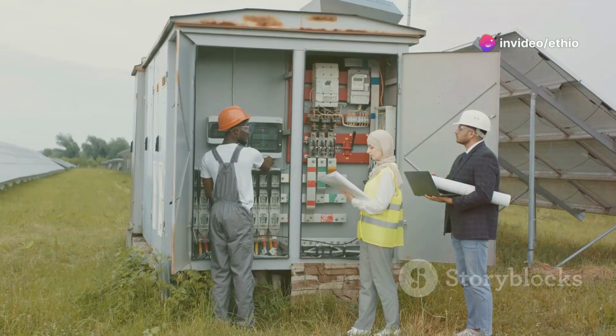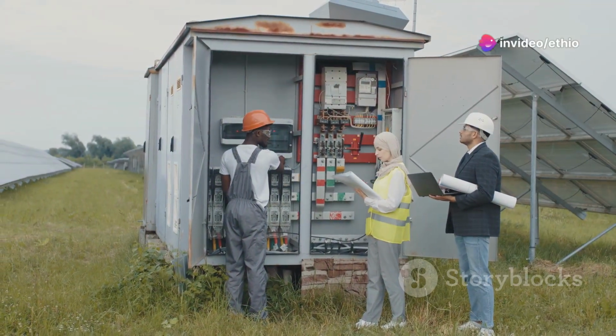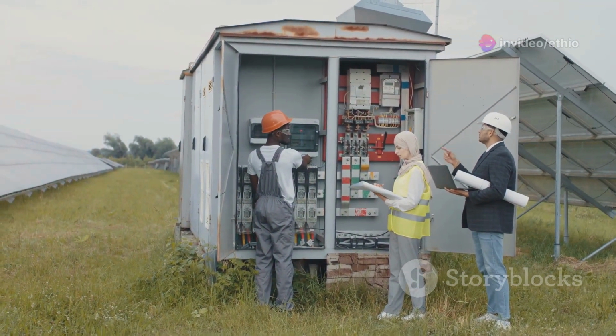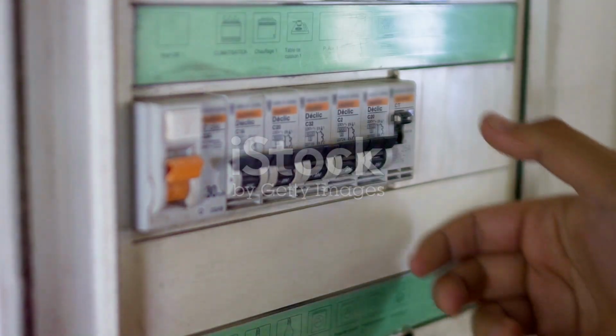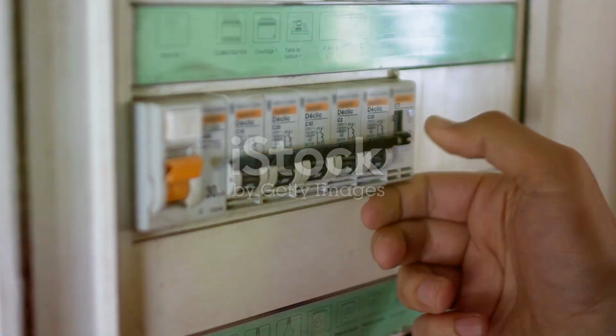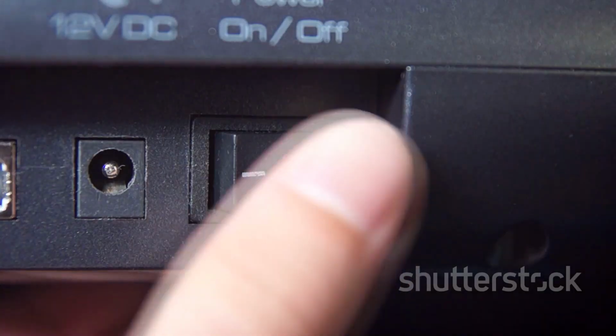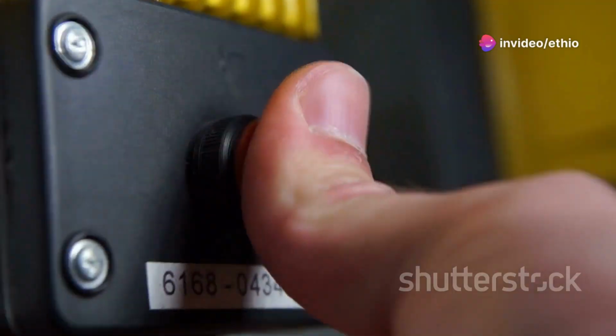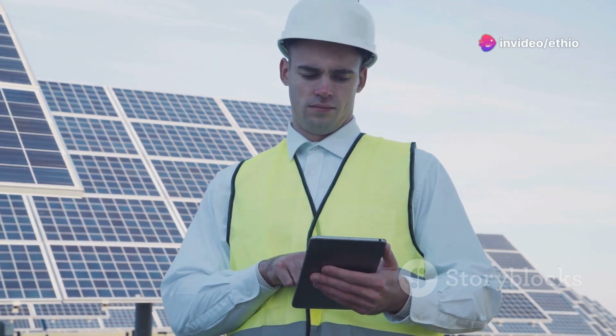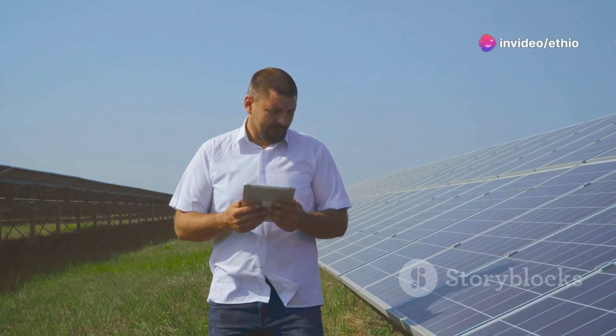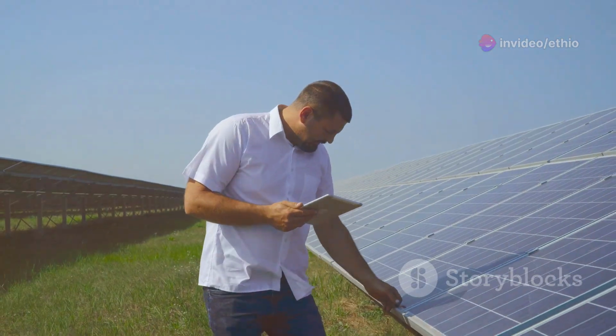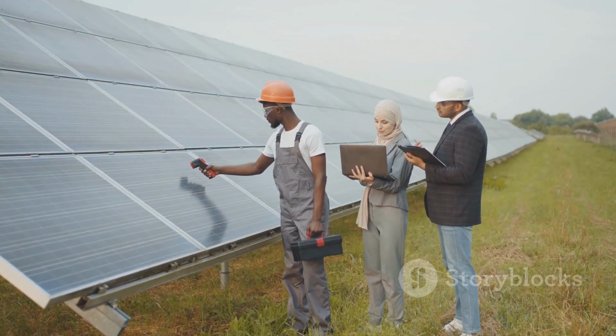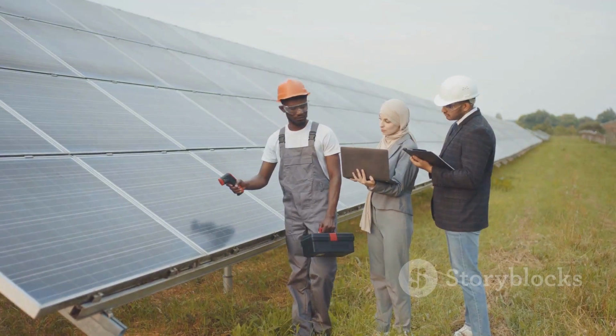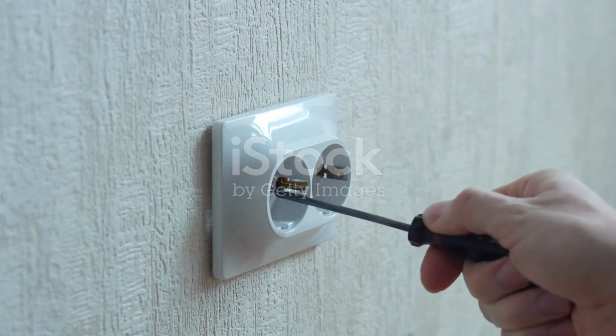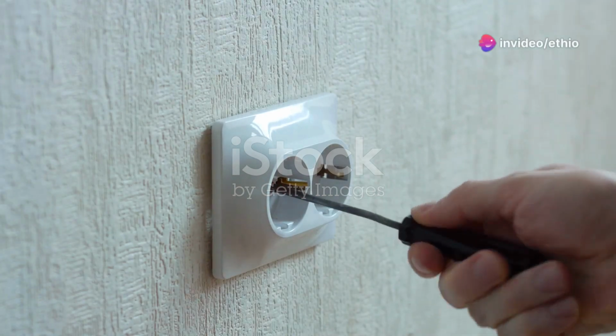After fixing your inverter, test the whole system. Turn everything back on, starting with the DC isolator, then the inverter, then the main switch. Wait for the inverter to start up. Watch the display to check for new errors or warnings. Use an app or monitoring tool if you have one. Compare the power output to your normal sunny day numbers. Plug in some appliances and make sure everything runs as it should.